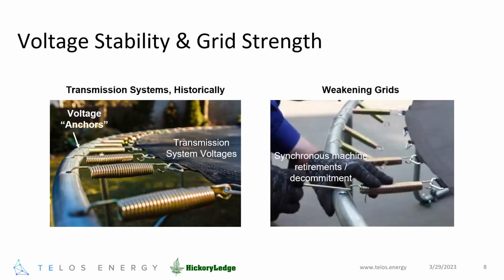So conventionally, with our weakening grid challenge, the retirement and decommitment of synchronous machines is akin to disconnecting some of those voltage anchors from the trampoline. So for the same loading, or the same disturbance, you have larger deflections in your trampoline, larger and faster deviations in your transmission system voltages, which manifests in control challenges for those resources.